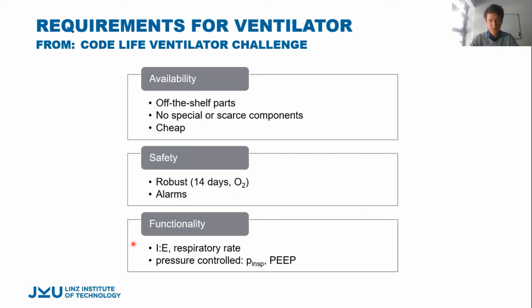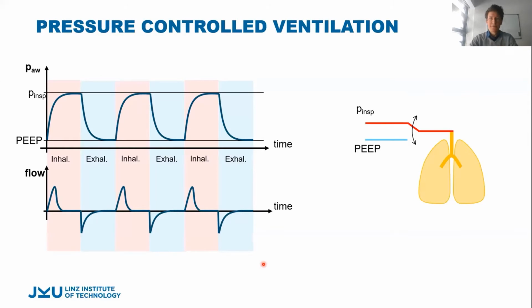So they also wrote about pressure controlled ventilation, which means that you have a lung which is basically connected in the inhalation phase to an inspiratory pressure, a high pressure, and in the exhalation phase, which is here in blue, to a lower pressure. This PEEP value is the positive end-expiratory pressure. So you basically inflate the lung with a higher pressure and then deflate it against a lower pressure, but this low pressure is still higher than the surrounding pressure, the atmosphere. So this is basically done in a very simple way by just connecting the lung to these pressure lines and switching them through.